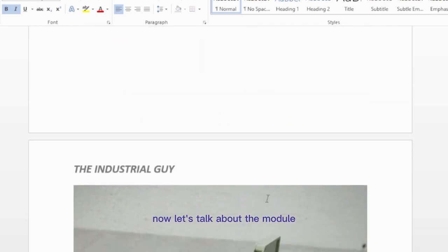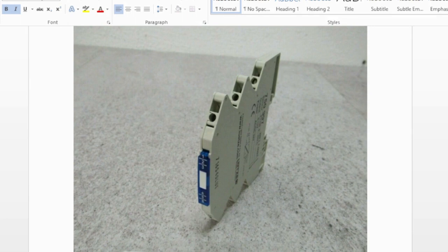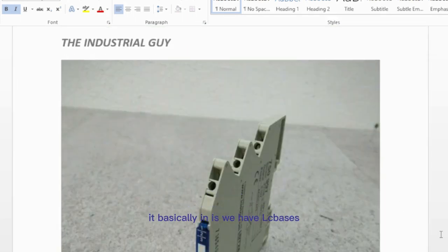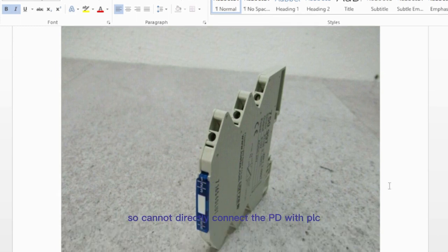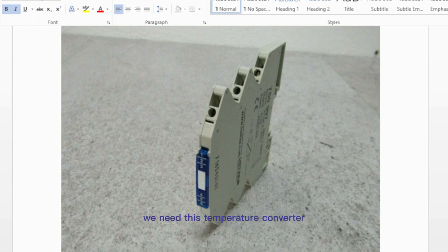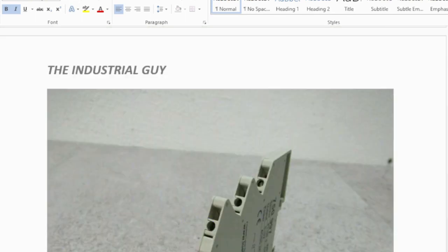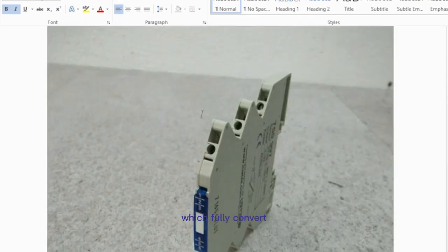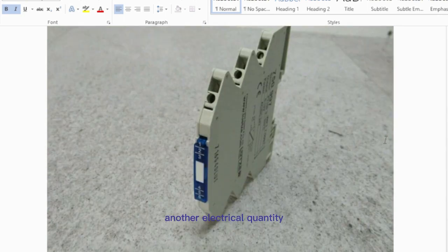Now let's talk about the module. Basically, in a PLC based system, we cannot directly connect the PT with the PLC or with a relay or with anything. We need this temperature converter kind of transducer, which usually converts one electrical quantity into another electrical quantity.